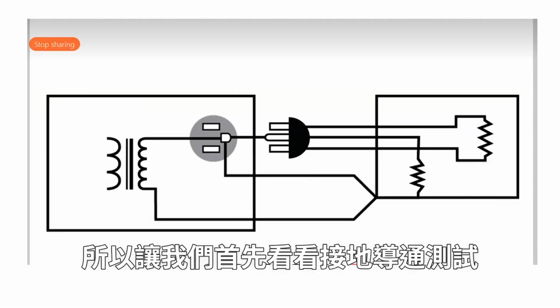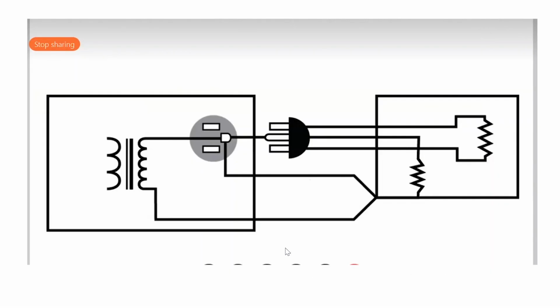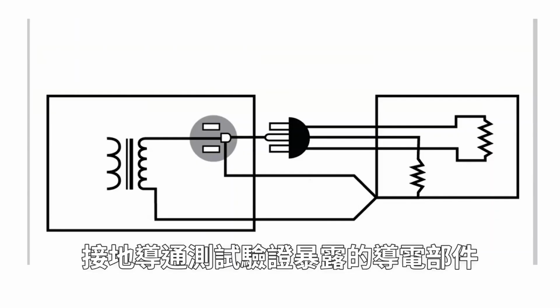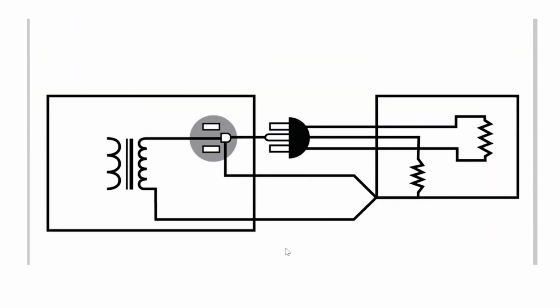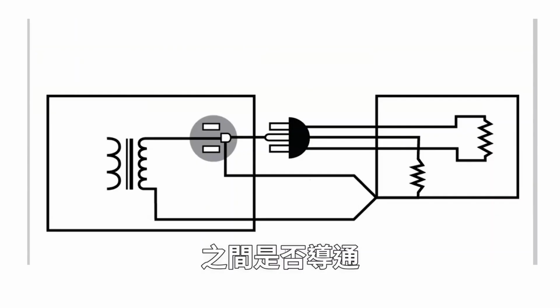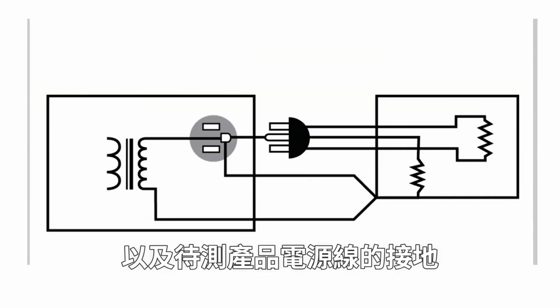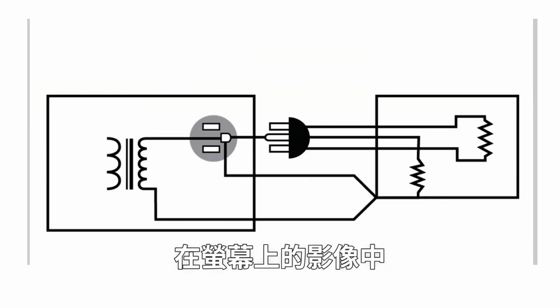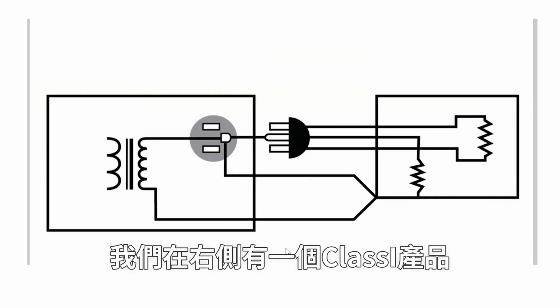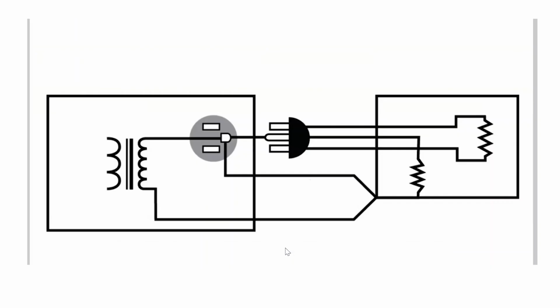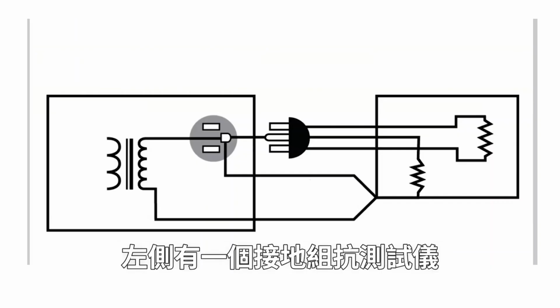Okay, so let's take a look at the ground continuity test first. The ground continuity test verifies a continuous connection between exposed conductive parts and the ground of the power cord on the product under test. In the image on the screen, we have a Class 1 product on the right side and a ground continuity tester on the left side.